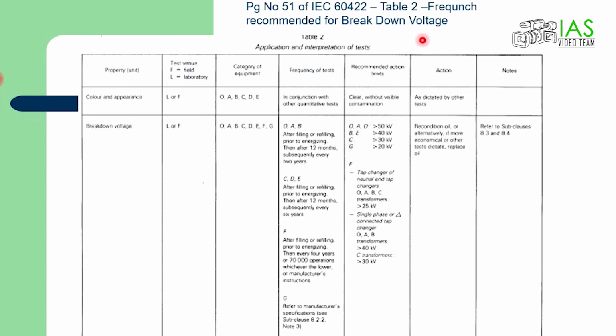IEC 60422 would give you, now take this breakdown voltage and categories O, A, B, C and whatever, and OAB, frequency of tests, right, is given in this column, and the values what it should be for each voltage category is given in the other column, right. Now, what is the breakdown voltage test?